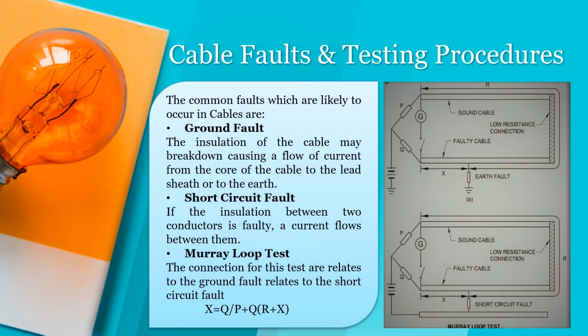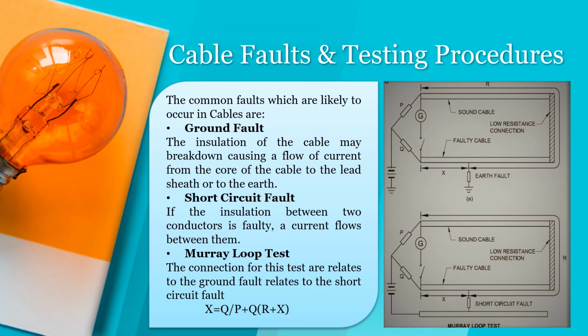The common faults which are likely to occur in underground cables are, first, ground fault: the insulation of the cable may break down, causing a flow of current from the core of the cable to the lead sheath or to the earth. Second, short circuit fault: if the insulation between two conductors is faulty, a current flows between them.